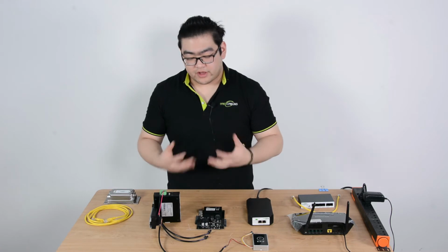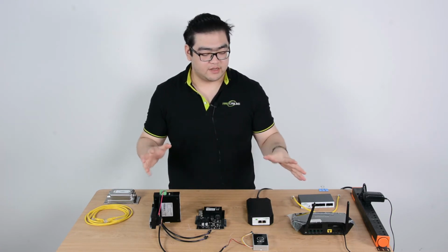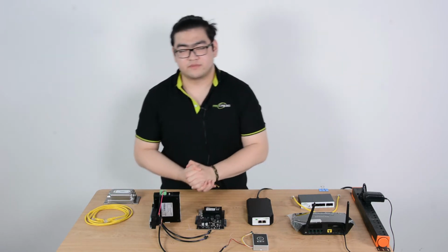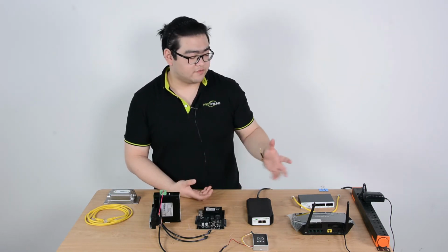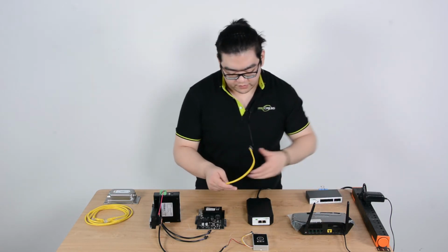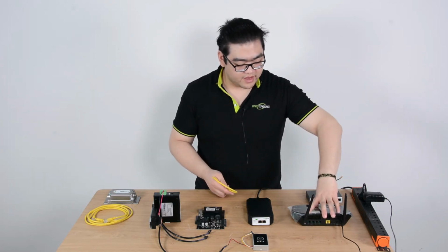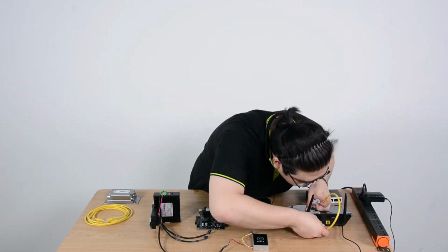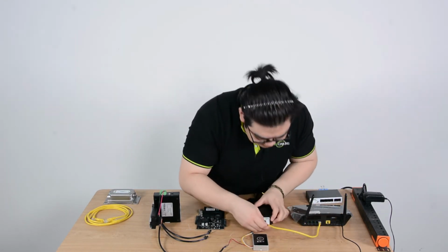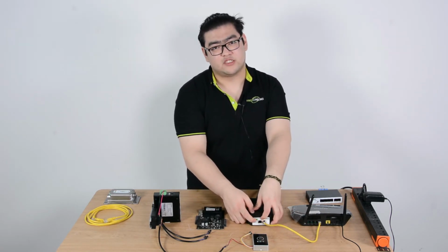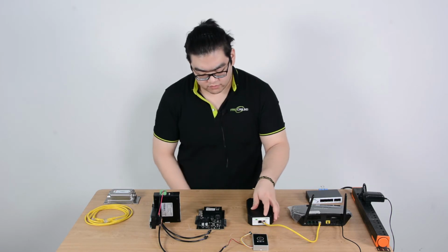All right, now let's walk you guys through the procedure for setting up this whole system, and you can see it step by step. So first of all, we're not going to use the PoE switch. We're going to use a router since we're having an injector here. So our router will have the data right here, and we will connect our router to our injector. So then we have our PoE signal ready with power and data getting ready to transmit out of this port.